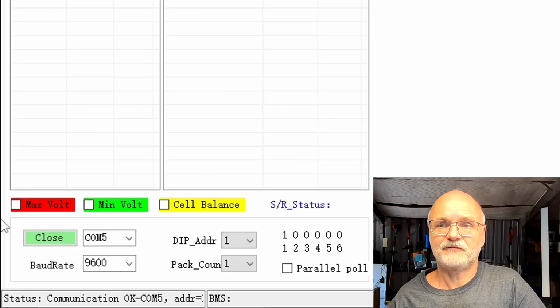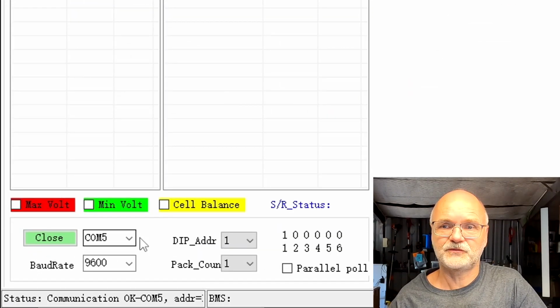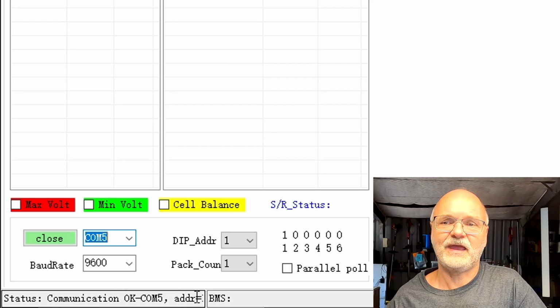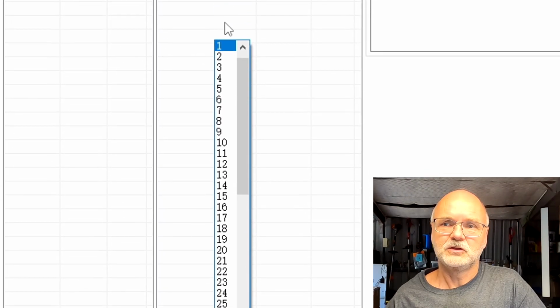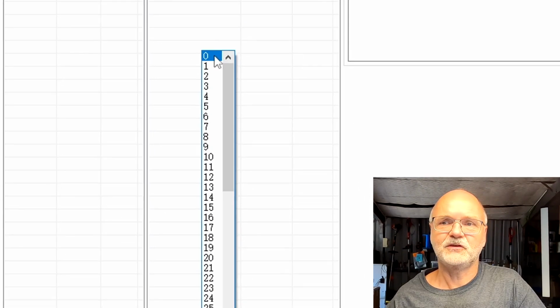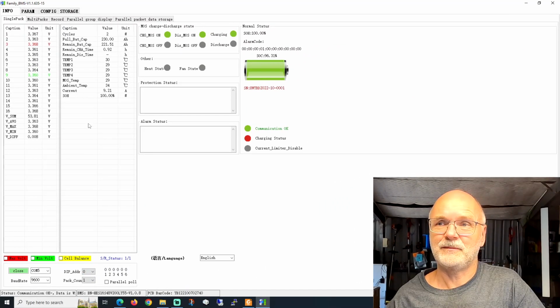Here in the bottom left-hand corner you set your COM ports, and it already says communication OK, but it says address fail, because we need to change the DIP address from 1 to 0. As soon as you do that, it connects to the BMS straight away and gives you all the information.